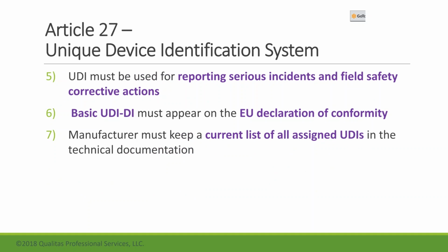And this is critical as well. And this is similar to the US requirement. The manufacturer must keep a current list of all assigned UDIs. It goes on to say in the technical documentation. And so you have to think, what is technical documentation in terms of the MDR?